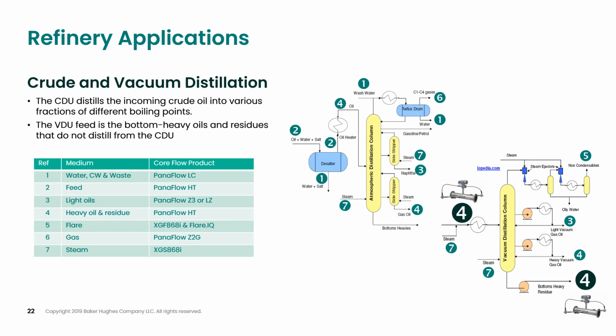Similar to the delayed coking unit, for water, we typically use our Panaflow LC liquid clamp-on ultrasonic flow meter for hazardous areas. For light oils such as naphtha and LCGO, we used either our Panaflow Z3 or LZ process-wetted ultrasonic flow meter. For the flare lines, we use our XGF 868i meter. For fuel gas, we would use our Panaflow Z2G process gas meter. For the steam line, we would use our XGS 868i ultrasonic flow meter for steam.